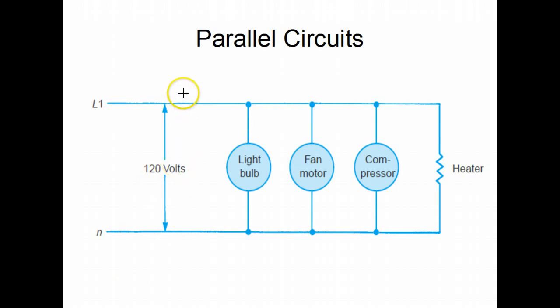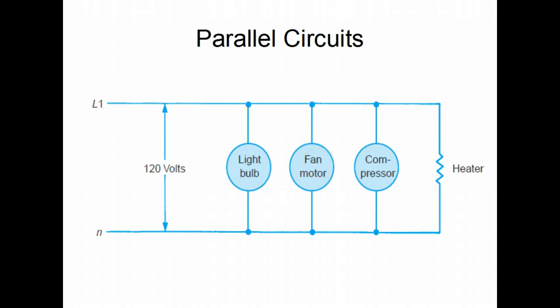If we had another light bulb added in series in this position, this light bulb would come on but it would take some of the voltage from the power source and drop that voltage — then this light bulb would be dim, this fan motor wouldn't run properly, nor would this compressor run properly. So all of the loads in an air conditioning circuit and in a schematic diagram are in parallel.